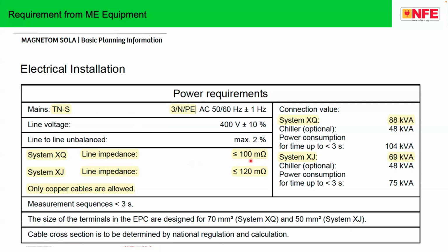One question which I seriously wanted to ask all the medical electrical equipment companies: are you seriously measuring the line impedance? The reason is, this machine has an inbuilt fuse inside. The purpose of the fuse is, once the machine catches fire, the fuse should blow or disconnect the supply much before the electrical appliance ignites fire. Now, if the line impedance is higher than this particular value, forget it, the fuse will not work. It becomes fire.